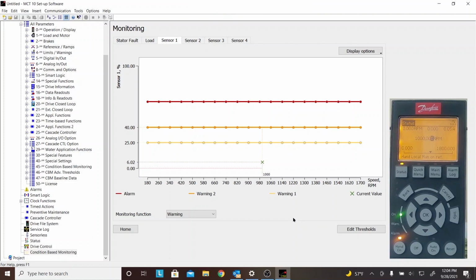So that is a great overview of what we're looking at with the keypad, with the drive running, and with the software MCT10 running on the drive, and the way you can use this as a tool, not only to easily program the drive with this plugin, but use it as a maintenance tool, even the Group 15, 16, and the condition-based monitoring all together as one whole maintenance tool for the machine itself. So great software, and we'll take questions after the demo.